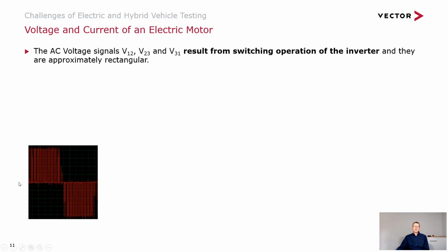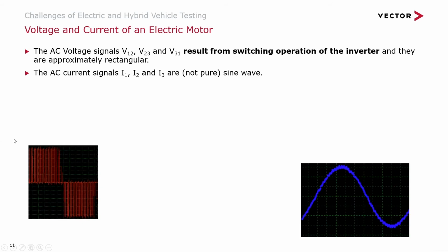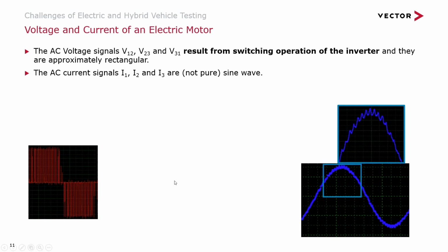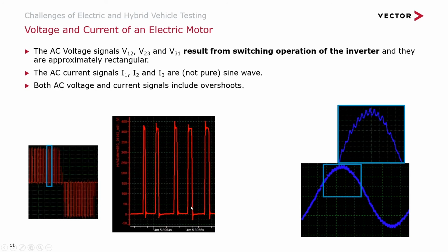So if we just take a sample here, the voltage between the phases is a result of this switched operation of the inverter, and it's approximately rectangular. We then have an AC current coming out. It's a sine wave, but it's not pure, so we have this ripple on top, which could affect our circuitry. And then if we look at our DC, our voltage chopped up, then we see we've got these spikes. And these spikes and ripples can excite resonant circuits in our motor, inverter and cabling. So really they should be monitored and suppressed if necessary.